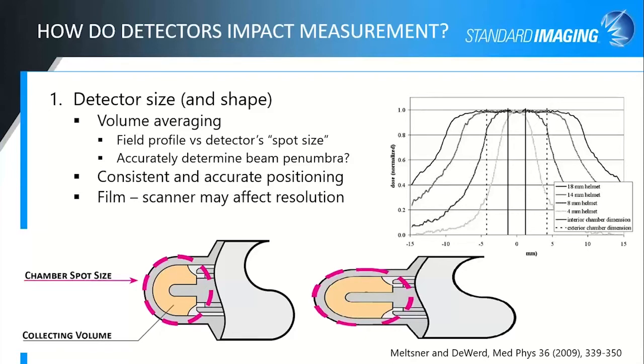The size of your detector also determines how accurately you are measuring your beam penumbra, because obviously a larger detector, larger integration in the direction of the penumbra, will include a little bit bigger smearing effect, a little more averaging as you're measuring that penumbra. Consistent and accurate positioning is critical, obviously, with your detectors.